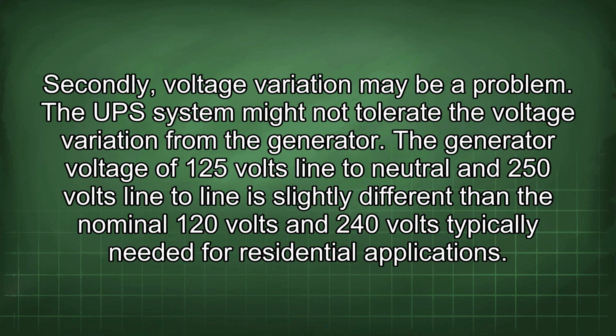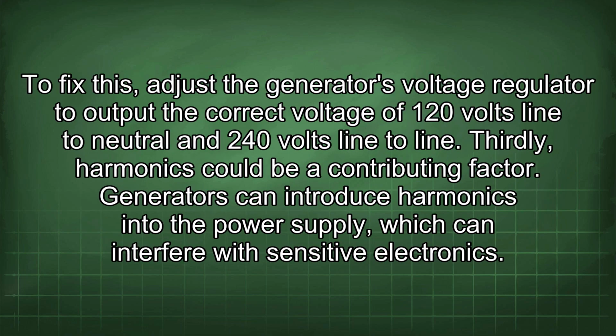Secondly, voltage variation may be a problem. The UPS system might not tolerate the voltage variation from the generator. The generator voltage of 125 volts line to neutral and 250 volts line to line is slightly different than the nominal 120 volts and 240 volts typically needed for residential applications. To fix this, adjust the generator's voltage regulator to output the correct voltage of 120 volts line to neutral and 240 volts line to line.